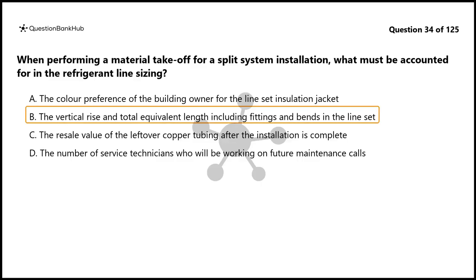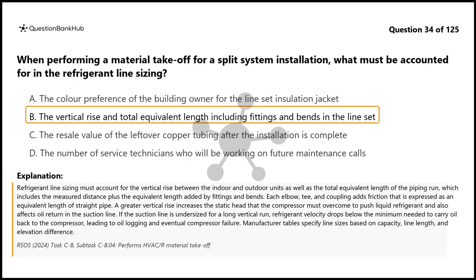The correct answer is B. Refrigerant line sizing must account for the vertical rise between the indoor and outdoor units as well as the total equivalent length of the piping run, which includes the measured distance plus the equivalent length added by fittings and bends. Each elbow, T, and coupling adds friction that is expressed as an equivalent length of straight pipe. A greater vertical rise increases the static head that the compressor must overcome to push liquid refrigerant and also affects oil return in the suction line.